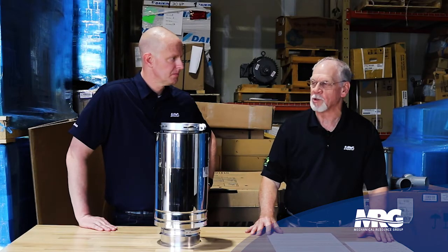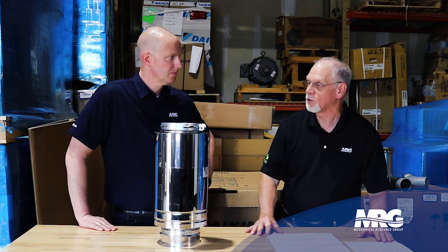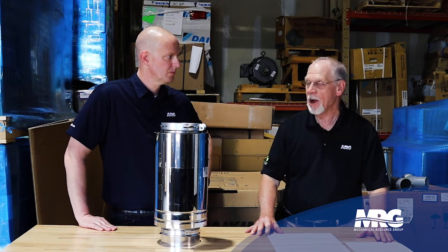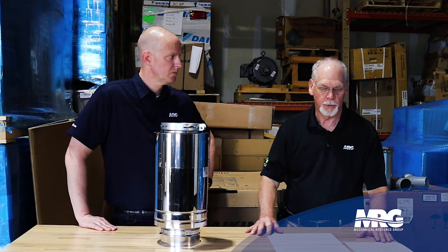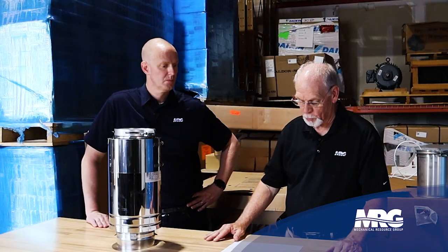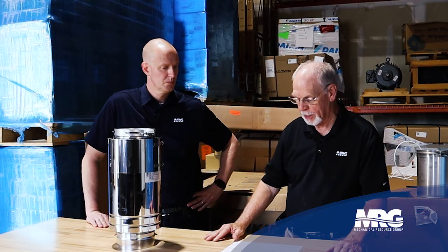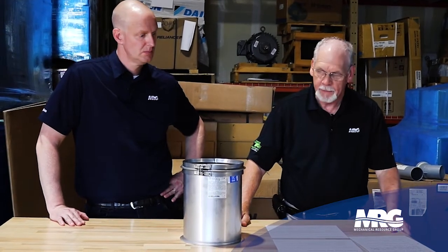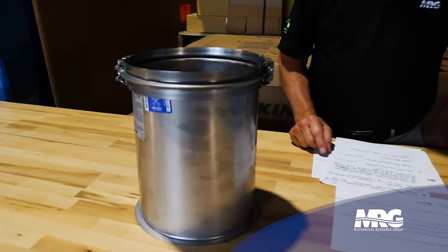On the condensing boilers, most of those do have a fan that helps to bring the air into the combustion chamber. They have what's called a closed combustion chamber, so that we're bringing in outside air to fuel the fire in the unit. But both those 1 and 2 are negative pressure. 1 is non-condensing, and 2 is condensing. When we move to the next category of Category 3 and Category 4, they're both positive pressure. So we have a little bit different joint for those.